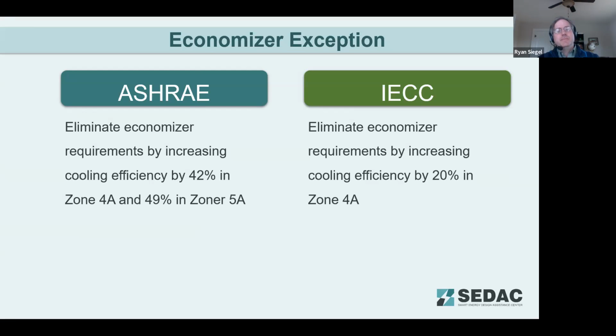The economizer exception: ASHRAE does have two exceptions for both climate zones 4 and 5, whereas IECC only has an exception for climate zone 4. So while ASHRAE does have exceptions for both 4 and 5, it does have a much higher threshold. I mean, understanding you have to be able to increase your cooling efficiency by 42 or 49%, that's a dramatic increase. Whereas the IECC just says, hey, as long as you're up to 20% better, that gets you past that threshold.